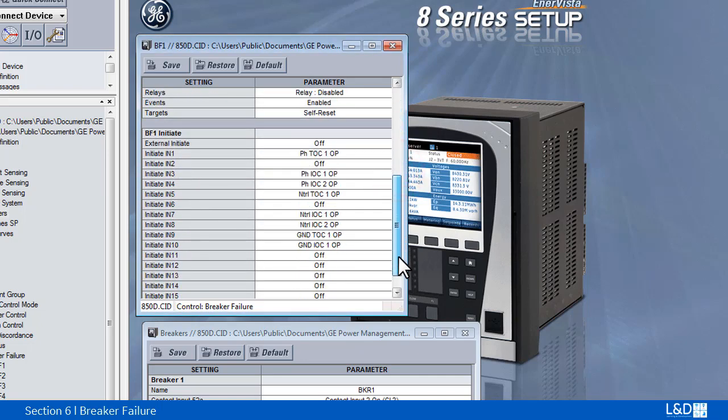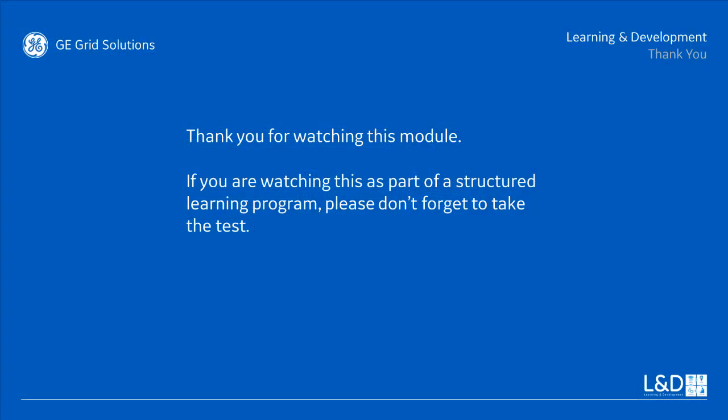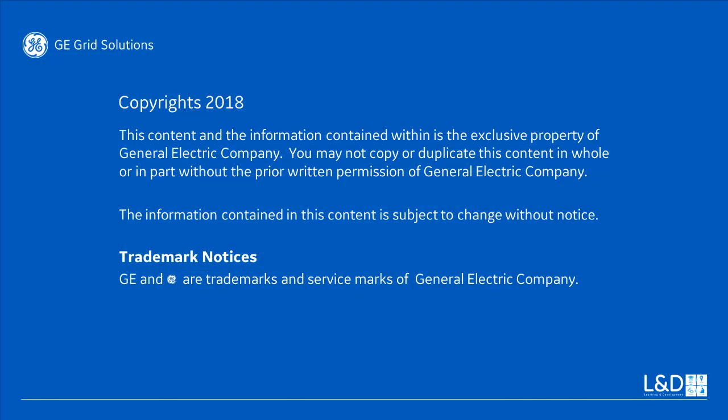Breaker failure initiation can be from external with flex operand or with 15 internal protection operands like the phase TOC, IOC operand or neutral TOC, IOC operand.